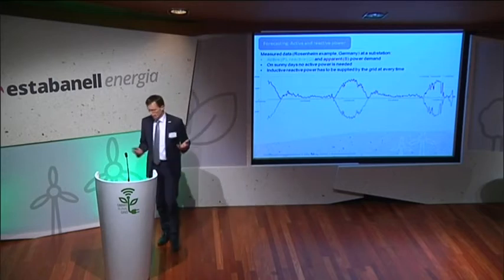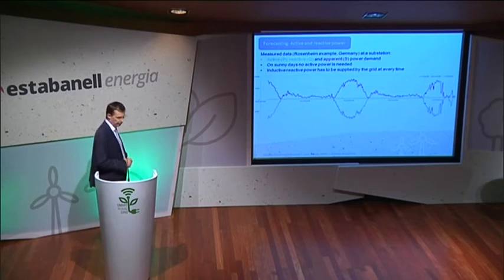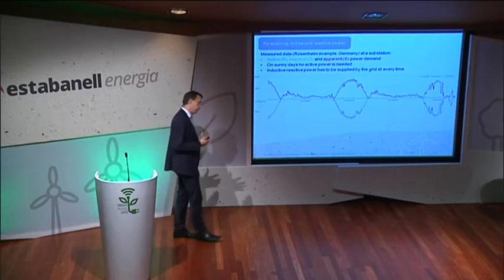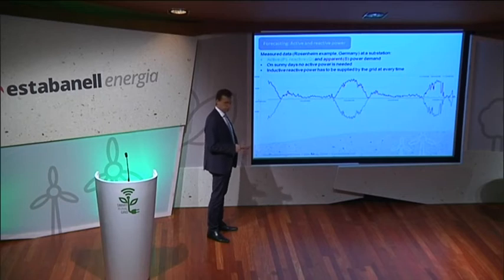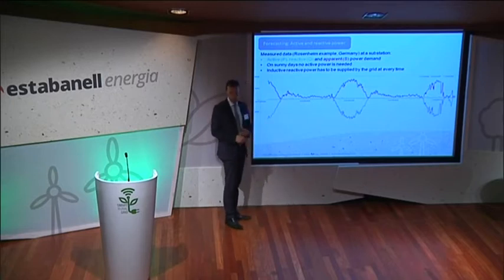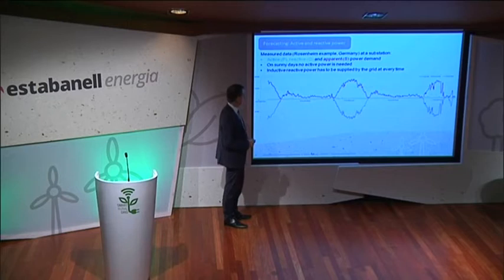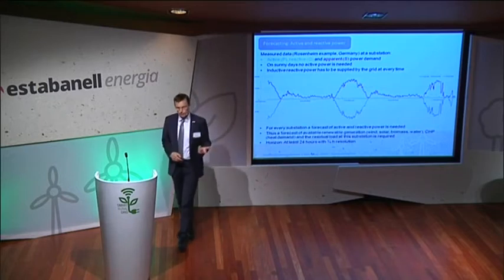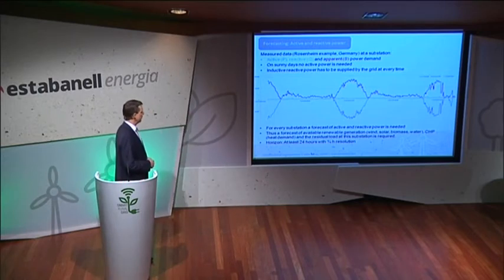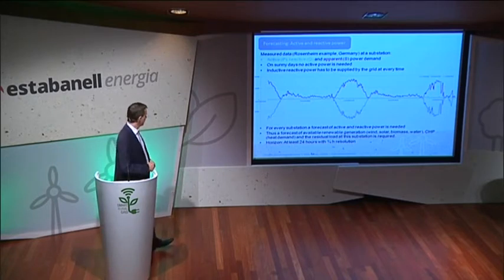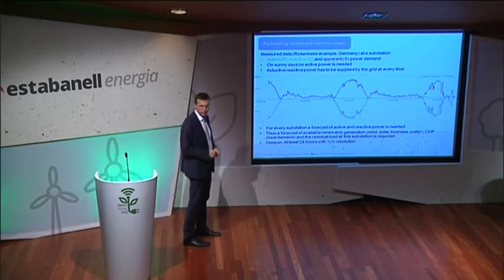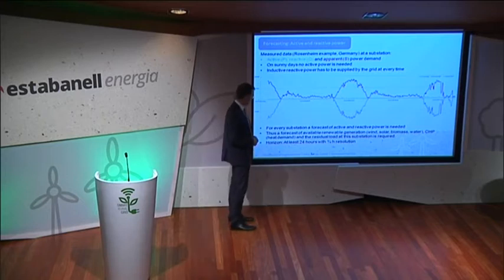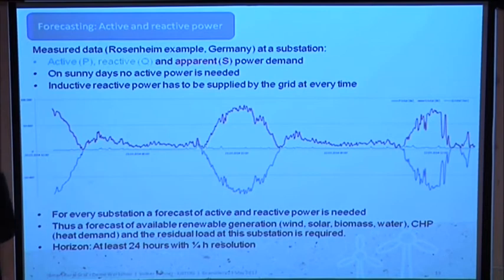Feeding back photovoltaic, or renewable energy at all, is often limited by the capability or capacity of the lines, which often have problems with voltage. Having problems with voltage, with a voltage band, means having problems with reactive power. So it's a good idea not only to forecast the active power, but also the reactive power. That's the reason why in this project we have forecasted both active and reactive, more or less for every load, every asset which was in the pilot area. And we have to do it at least for the next 24 hours, which was the aim, in a resolution of 15 minutes, because we want to use the whole cycle of a battery.